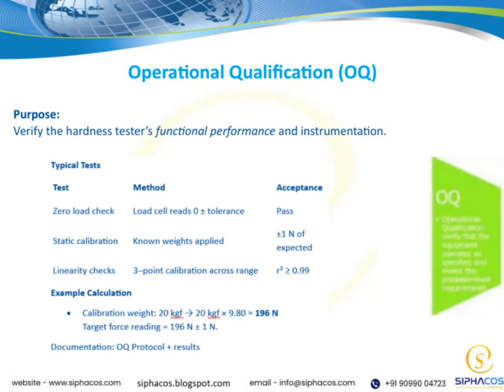Now, let's move on to operational qualification, or OQ for short. The main purpose of OQ is to verify that the hardness tester is functioning properly and that its instrumentation is accurate and reliable. Essentially, we're checking that the equipment performs as expected under real-world conditions. This step is crucial because it ensures the measurements we obtain are valid and consistent.